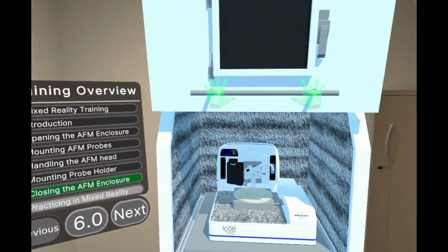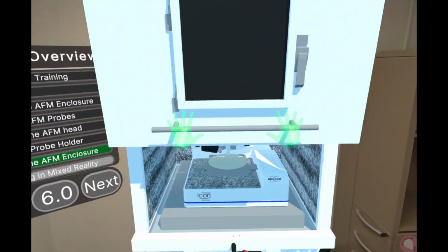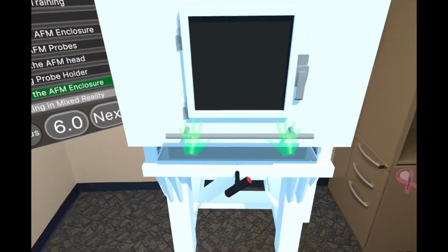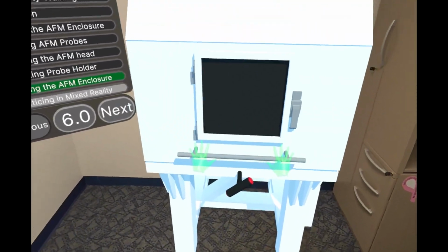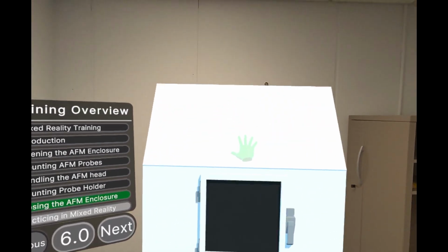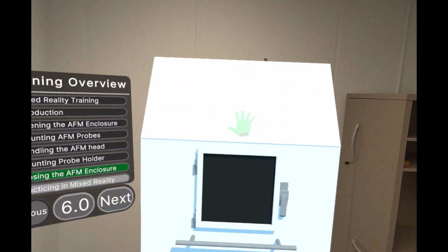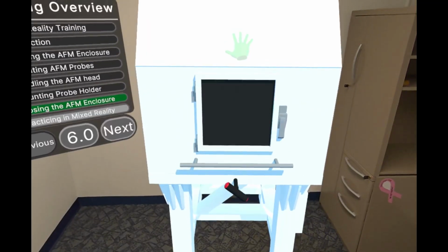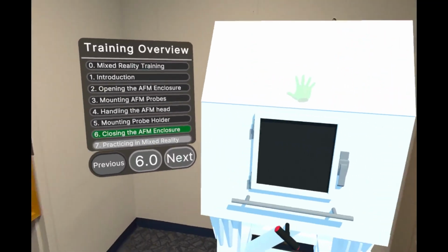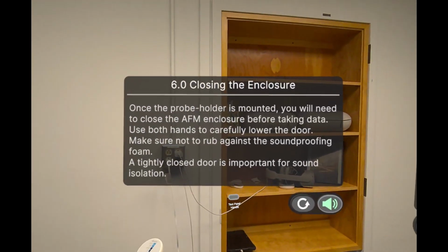Closing the enclosure door. Once the head is installed, we'll close the door. Lower the AFM door carefully without smashing it into our soundproofing as you come down. We want to avoid rubbing the door against the soundproofing foam as that tears easily. That's why it's covered in tape.